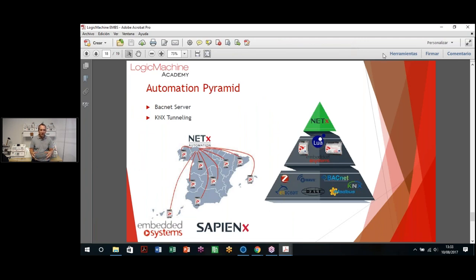In the image, you have an image of Spain, but never mind if it's any country or the entire world. If you have 1,000 devices, you may need an upper solution, or you may need a way to upload all this data to a central platform where you can manage and integrate everything together, even if they are in separated spaces. So what we are going to show in 2 minutes is how easy it is to do it when you're using BACnet or even KNX. We can do it both ways, but in BACnet it's very easy to show and demonstrate it.